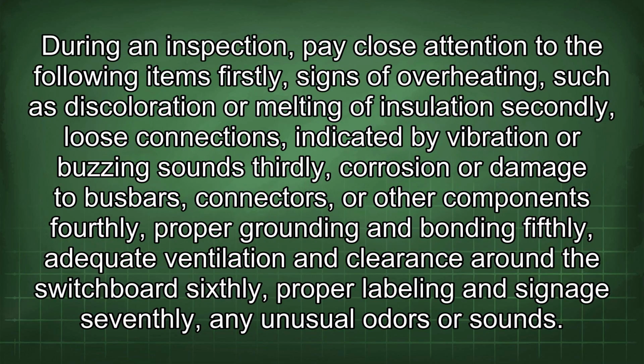During an inspection, pay close attention to the following items. Firstly, signs of overheating such as discoloration or melting of insulation. Secondly, loose connections indicated by vibration or buzzing sounds. Thirdly, corrosion or damage to busbars, connectors, or other components. Fourthly, proper grounding and bonding. Fifthly, adequate ventilation and clearance around the switchboard. Sixthly, proper labeling and signage. Seventhly, any unusual odors or sounds.